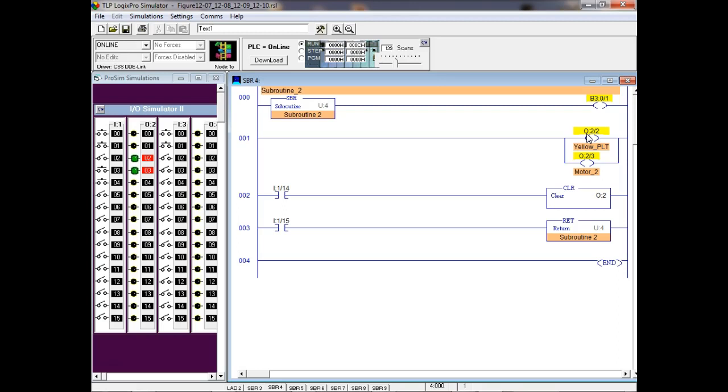So when the PLC is scanning, all it's doing is looking at that output 0, and if it sees a 1, it turns that output on. If it sees a 0, it turns that output off. Now by normal scan, we're updating that output file with outputs, right? With O instructions. But we have access to that. So I could come up here and basically do anything I wanted to. I'll show y'all that in a minute.